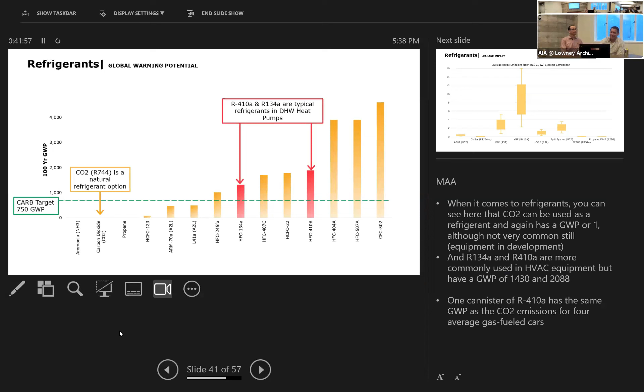What that means is that a lot of the equipment we're using in projects right now, these air source heat pumps, are using these typical refrigerants. They can no longer be used as of January 1st, 2024. So there's a bit of a market shift happening here with manufacturers and us. We're all working together trying to figure this out, but that's what's happening. If you do have a 410A machine, you'll still be able to get hold of the refrigerant for quite a long time, but you won't be able to buy new 410A equipment. And it is a bit of a worry because the replacement equipment isn't commercially available yet when time's running out, right? And we've got long lead times.